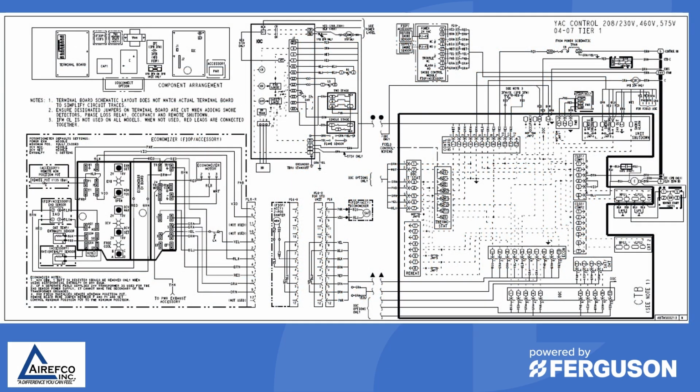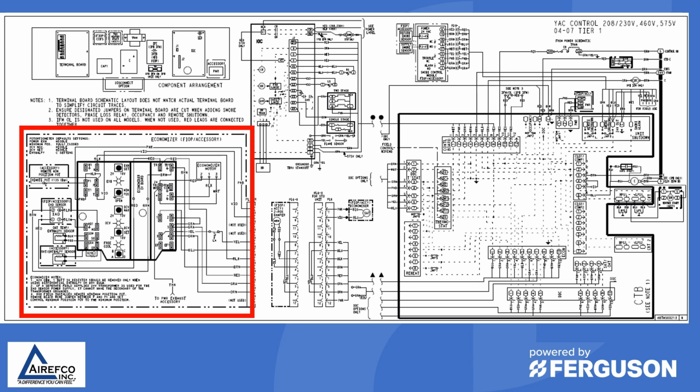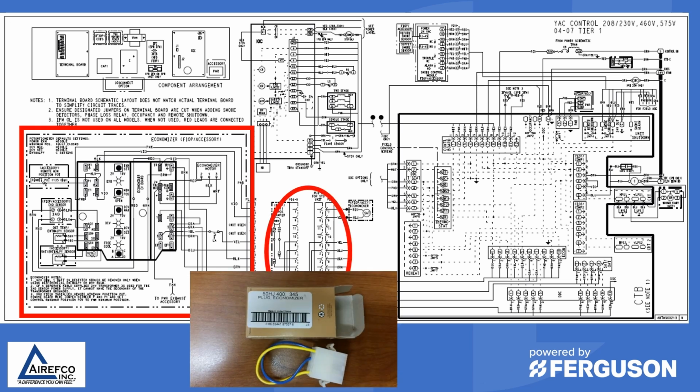Remember this diagram at the beginning of the video? You can also troubleshoot a diagram or a system like this by isolation. One of the first things you should do is get rid of the economizer. This will take a complete control system out of the picture. By using the bypass plug, which you should keep when you install an economizer, you can plug the bypass plug in, which will totally bypass the economizer. So if there is a short or a problem in the economizer or the economizer wiring, this is a quick and easy way to find that out.